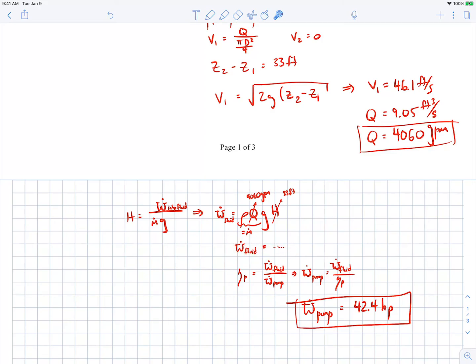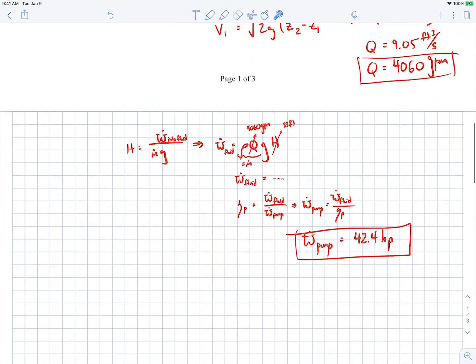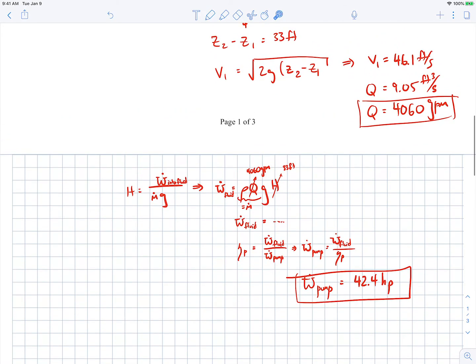We rearrange this equation to solve for the power in the fluid. We know the density of water, we know the flow rate we're dealing with, we know the acceleration due to gravity, we know the head rise was 33 feet. We can solve for the power into the fluid, but that's not the power into the pump. We know the efficiency of the pump is how much power gets into the fluid versus how much power we put into the pump. When you plug in all the numbers and do the unit conversions, it comes out to be just over 42 horsepower into the pump.